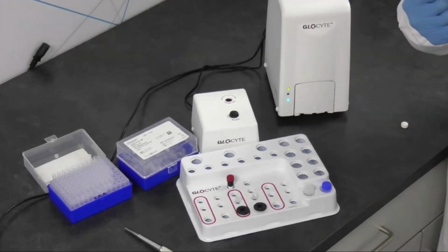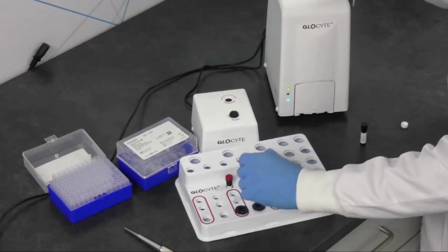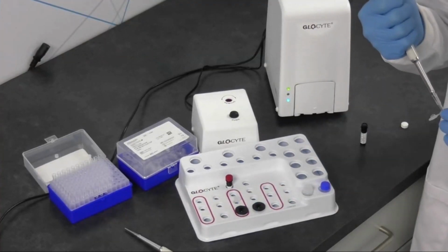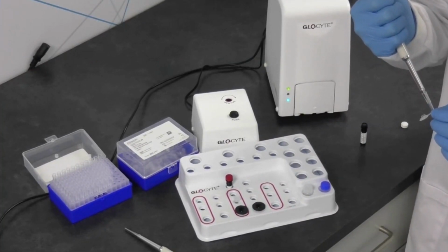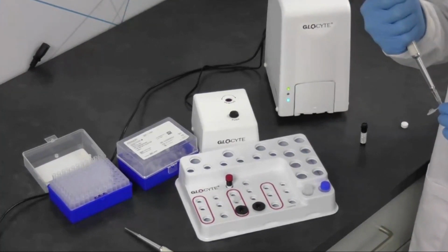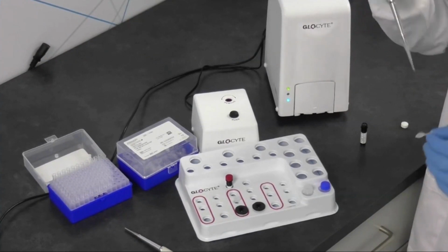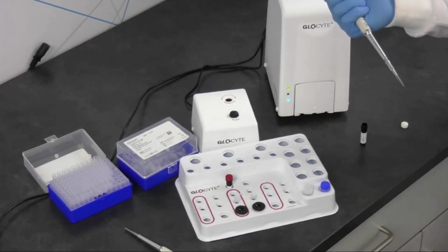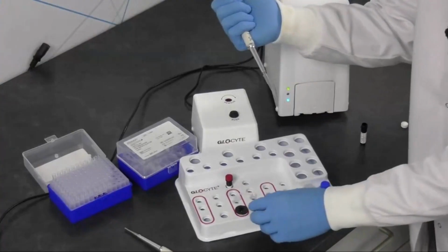And in the meantime, while we let that 3 minutes go, we'll go ahead and add our white cell reagent to our other sample cup. And again, we're going to add that in, and we're going to mix it 5 times. And then we're going to pre-wet that 3 times and just take up 30 microliters of sample. Because the white cell reagent directly stains the nucleus of our nucleated cells, we don't really have to worry about letting it sit around for the 3 minutes.